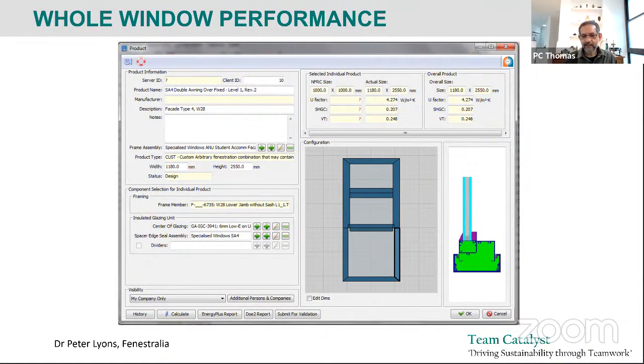And typically, the glazing supplier, the glazing contractor in Australia, is asked to provide a therm analysis where he finds out what is the frame performance, and then he combines it with the glass or the double glazing system that he's been asked to use, and then it'll give him a combined curtain wall performance, and that'll come out as exactly these 3 values: U value, solar heat gain coefficient, and visible light transmission.